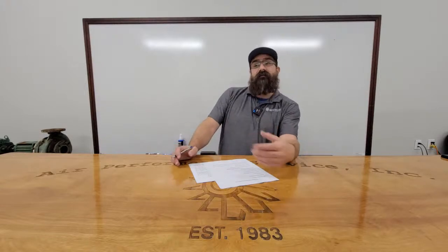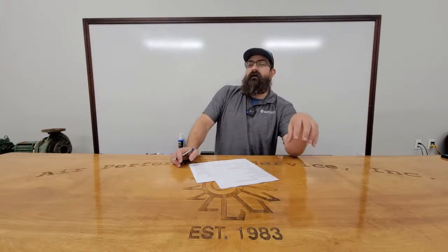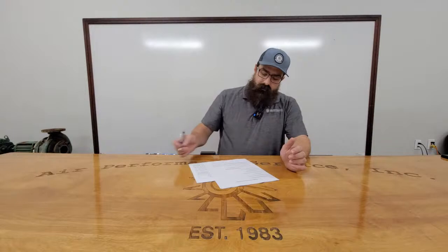So a relief fan is definitely going to be building pressure, or a return damper could be that way as well. But a return fan on an air handler, like I said, most of the time they're constant volume. They're just circulating air. But when they're not, they're still static pressure control on the building pressure side.